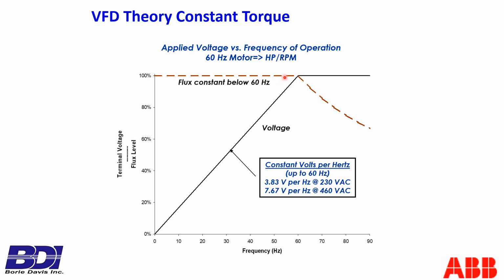And this brown dash line represents the available torque, and you see for all speeds less than 60 hertz, full torque is available for the same reasons of those things we did earlier. Remember the load and the distance where I took the 100 pounds, or you took it, and I said walk across the room in 1 minute, and that took 10,000 foot-pounds of work. Okay, that was the power required in the application. And then I gave you the same load, 100 pounds, but said take 2 minutes to get across the room. Well, that meant in 1 minute you only went 50 feet. 100 pounds, 50 feet was 5,000 foot-pounds.